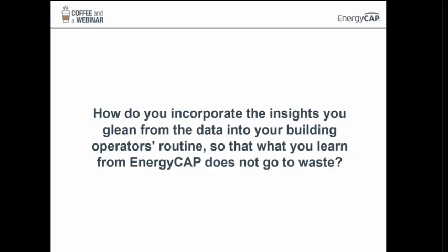You don't need a control center and someone sitting there 24/7 monitoring all these different systems. What you need is a look back every morning at yesterday's interval data, and simply by looking at 15-minute interval data from yesterday or the past weekend, you can spot some things that can probably save you some money immediately.